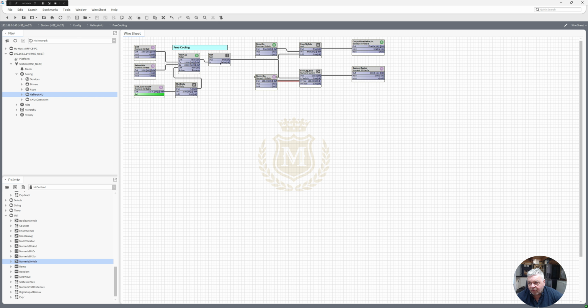So we can't do free cooling now, it's impossible. We're in a situation now where the recirc's back, and it's recircing the heat basically back to the room, and mixing of course with outside air. We can go on and on with this, but for the simple logic, that is your free cooling.